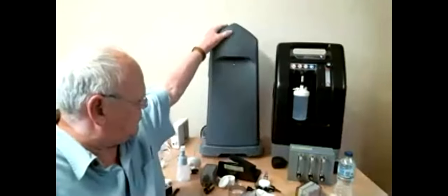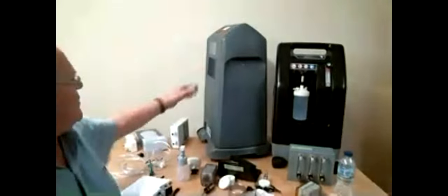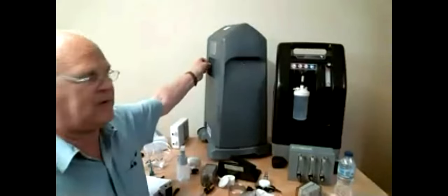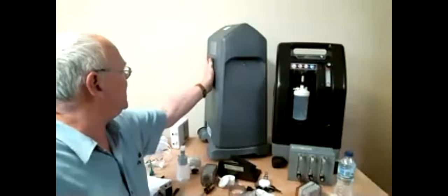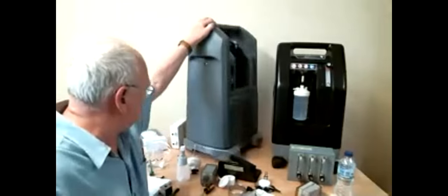Thanks, Robert. Had a follow-up question about the positioning of the concentrators close to curtains or walls. Robert, do you mind just spinning it around again and demonstrating the air inlet and why that's important? So you've got the air inlet here through the foam filter. If I put this back against the wall, flat against the wall, then it restricts the airflow through it. And that is a real issue to the machine itself.